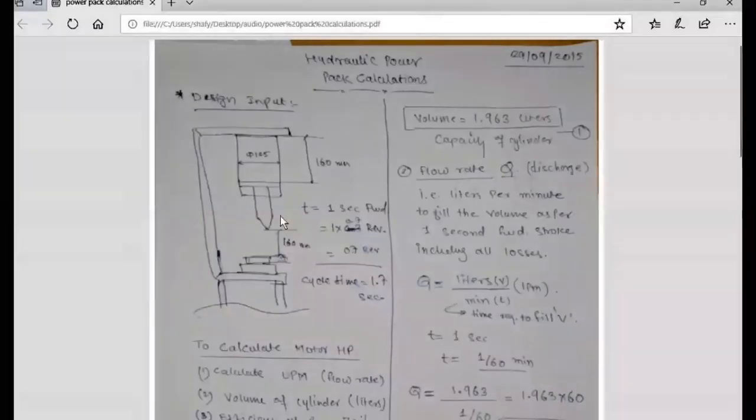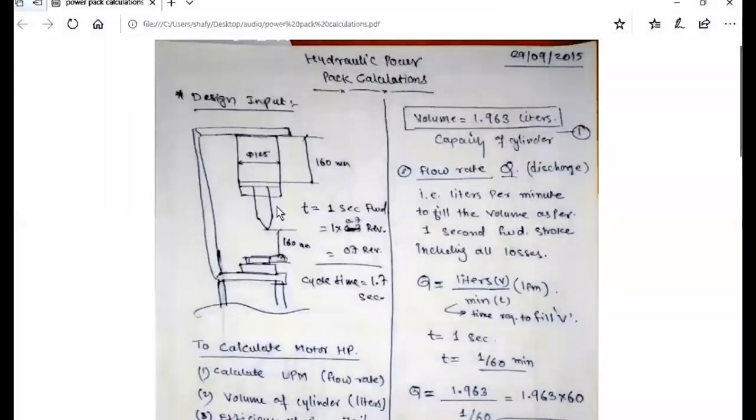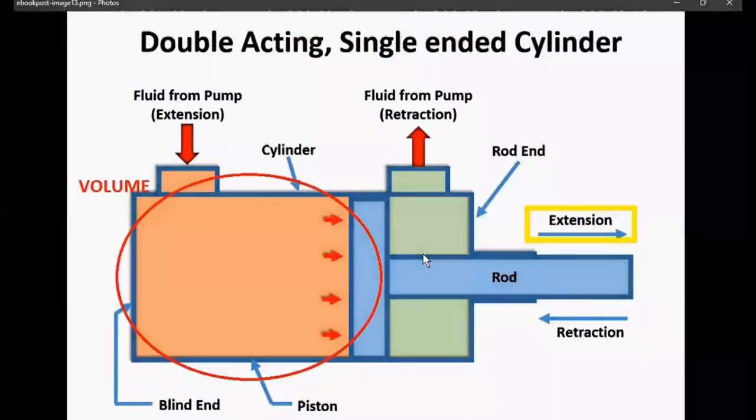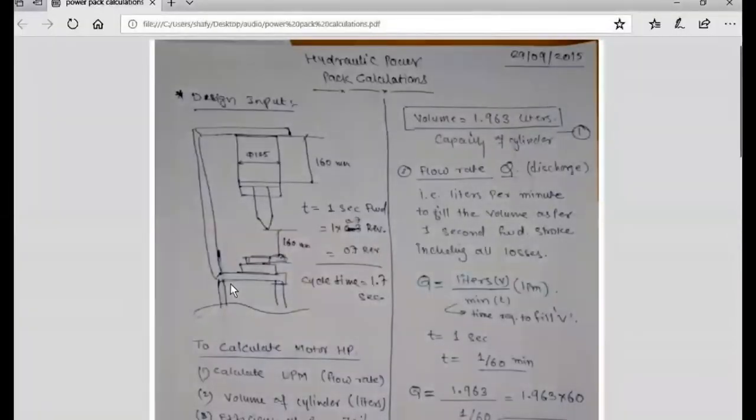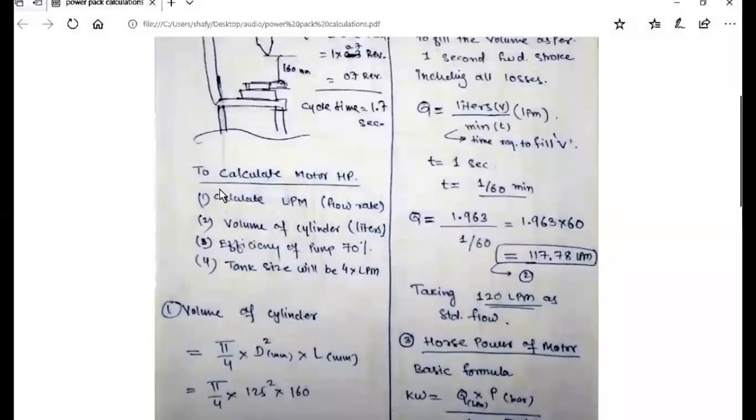So this is the volume of the cylinder which should be filled in one second because the stroke time is one second. And when this cylinder is going forward, it will retract in less than one second because we have piston rod also. The piston rod part is reduced to calculate the motor horsepower.